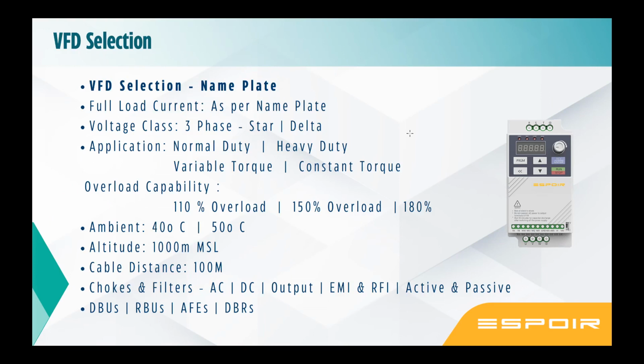There are discoms that have started penalizing customers for harmonic compliances and power quality compliances. Power quality compliance is one, but harmonic compliance is much more harmful to a grid as well as your equipment. There are other accessories, which are DBUs, dynamic braking units. In any application where you need to stop the system much before its inertia, it is going to work in a regen mode and you need to dissipate the energy somewhere. To do that, you need a dynamic braking unit. These DBUs divert the regen energy into a resistor. So the right selection of a DBU and a DBR as per the application is very important.